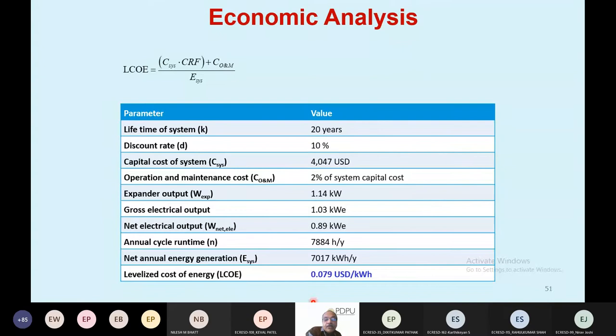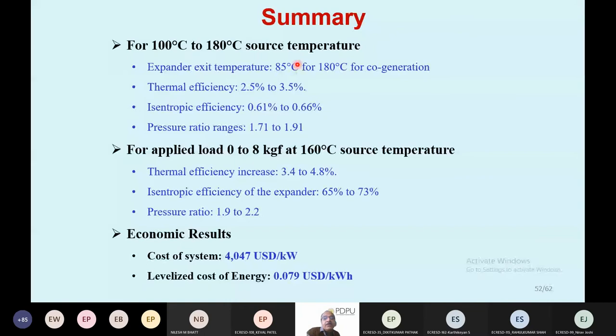Based on this, if the heat source temperature is between 85 and 180 degrees, the thermal efficiency is very low because losses are high at small scale. Increasing capacity can further increase this efficiency. Therefore an ORC around or below 1 kilowatt is not suitable; it should be around 5 or 10 kilowatts for much better efficiency. Also, if the source temperature is around 160 degrees centigrade, efficiency will further increase. From the economic results, the cost comes to about 0.08 US dollars, or around 6 rupees per unit, which is quite high mainly because the expander cost is high and not indigenously manufactured. Once Indian industries produce it, the price can go further downward.